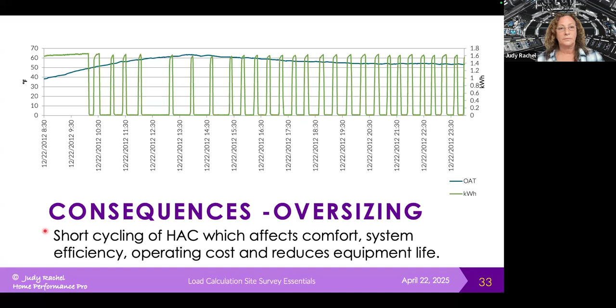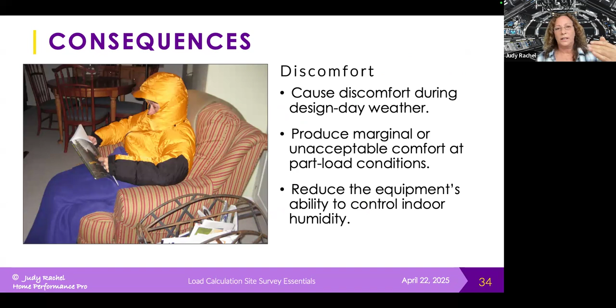At our design conditions, we're still not going to be comfortable in our homes. At our part load conditions, we're only going to get maybe marginal or just completely uncomfortable conditions in our buildings. And we're reducing the equipment's ability to control the indoor humidity when we oversize equipment. In our dry climate, it means that we're not getting as much sensible capacity out of the equipment as we can, and we're removing too much moisture from our homes if we're getting any latent.